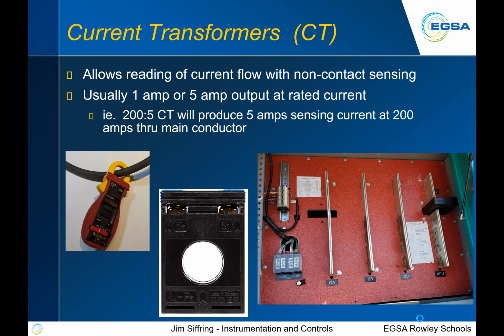A current transformer is a device that allows you to read the current flow through a conductor, a non-contact sensing device. Typically they're rated with a 1 or 5 amp output and some sort of an input. So if you see, for example, a device that says 200 to 5 on it, it means that at 200 amps, if you've got a conductor going through the hole in the middle of the black device in the center graphic, and you flow 200 amps through that conductor, then you will get a 5 amp output on the connecting pins on the top of that thing. So that's a 200 to 5 CT.